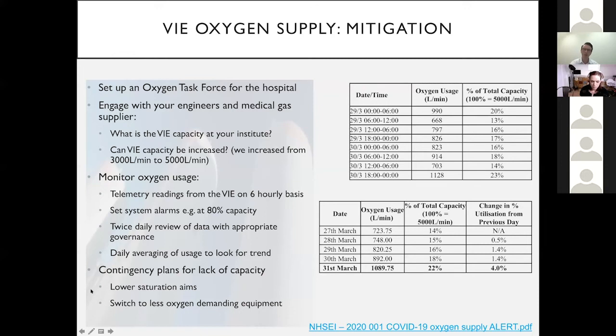Alongside that, we developed a system to measure oxygen usage on a 6-hourly basis, averaged over 24 hours. That allowed us to look at both the percentage of capacity used and trends in use, so we could look at increased use over days and predict when we might have an issue.